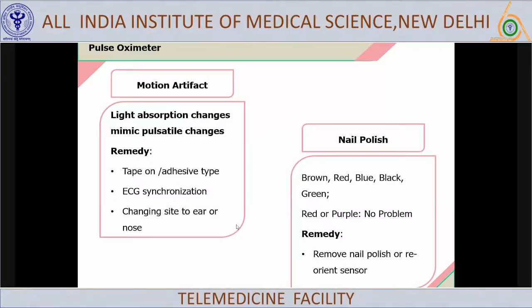Motion artifact. Sometimes the patient may be shivering because they may have fever. In those situations, whenever the finger on which you have applied the probe moves, they may show a wrong reading. So always be cautious about it. The application of nail polish, especially when it is brown, red, blue, black, or green, will again give wrong readings. Either remove it or apply the probe at a different place.